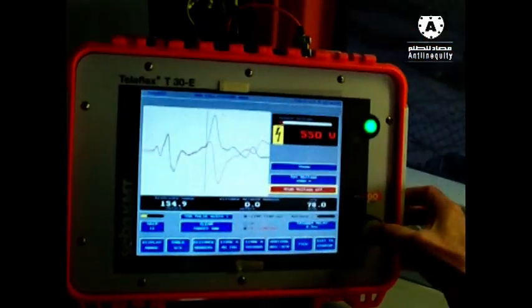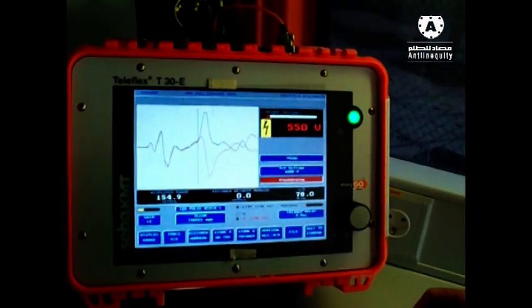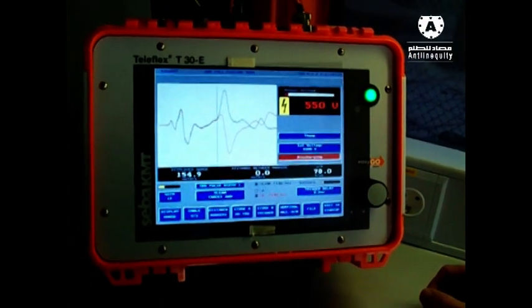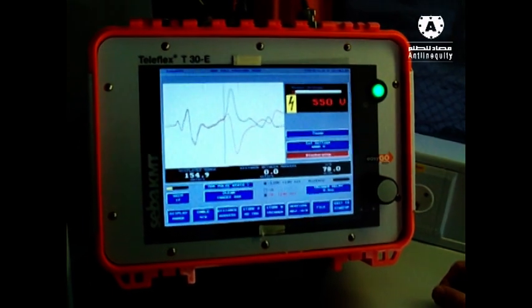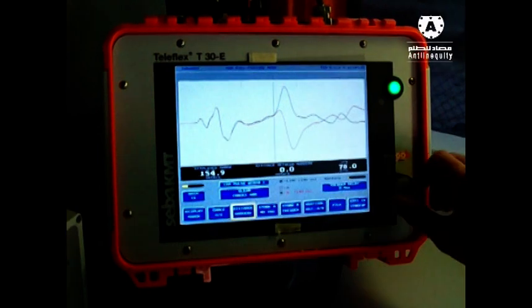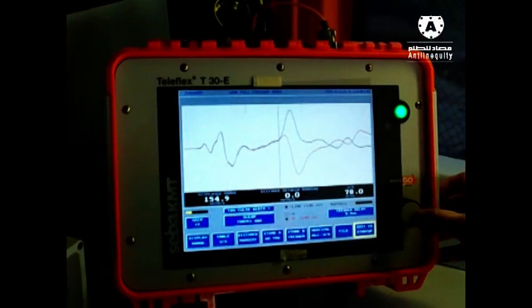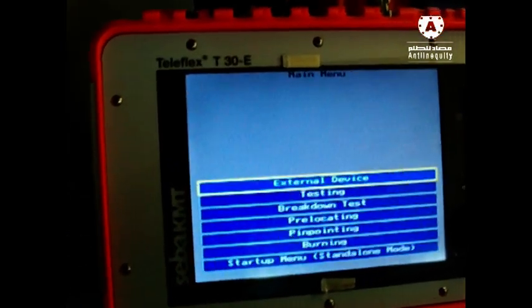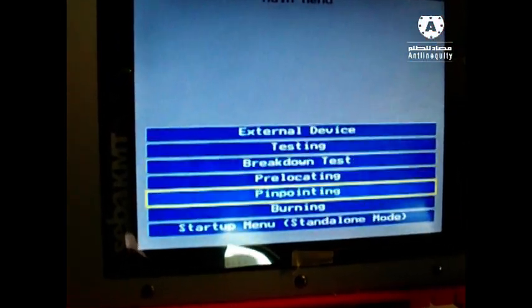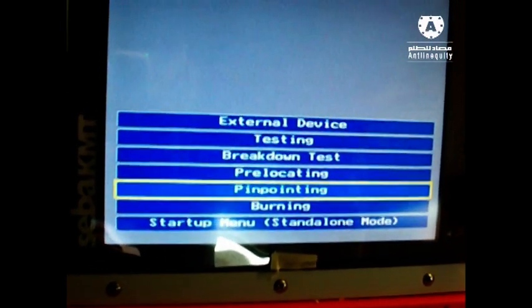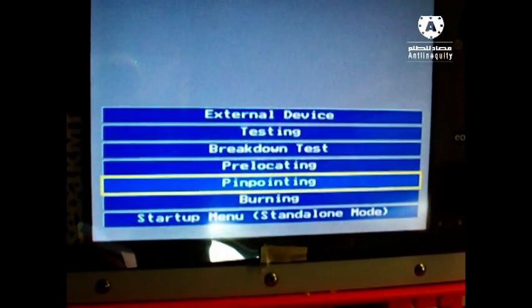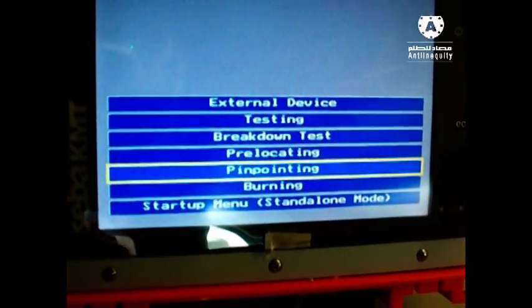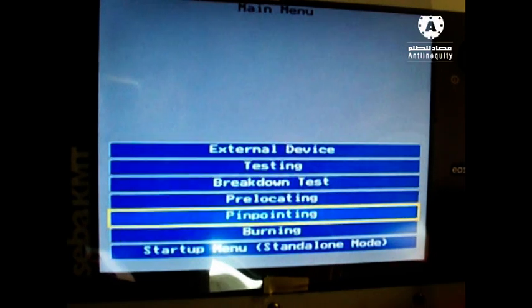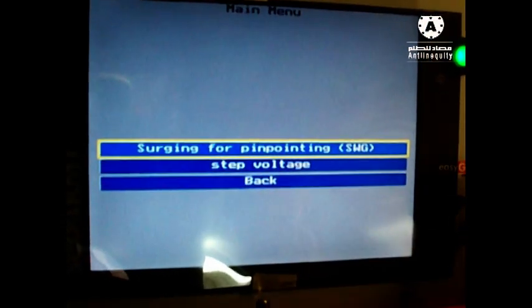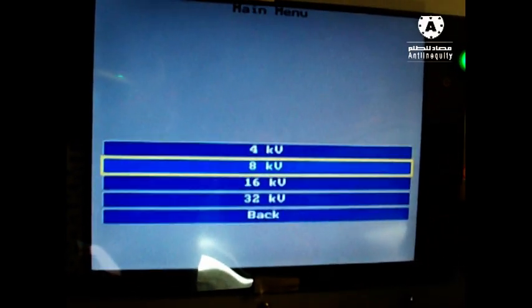that's it for pre-location. After we get all the information, we can discharge again. Still discharging. Okay, and then we go back to the main menu. The next step is now pinpointing. Pinpointing means we give a very big shot into our cable, into our fault. We get a flashover and we detect the sound of the flashover by a digiphone. So remember the last voltage we adjusted, we used 8 kV.